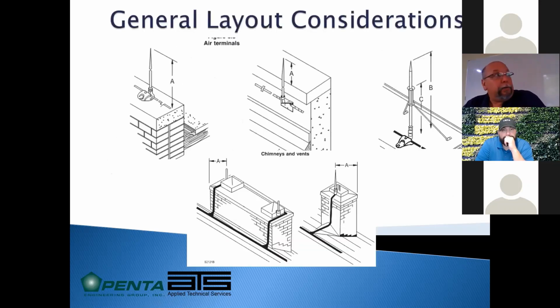So general layout considerations: the air terminals need to stick 10 inches above the object they're protecting. They need to be within 2 feet of the building perimeter and roof edges. So on chimneys, they need to be within 2 feet of the edges, also on mechanical equipment. If an air terminal is more than 24 inches tall, it needs to be supported at least midway up.